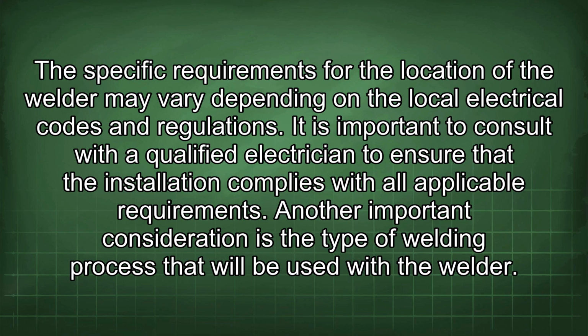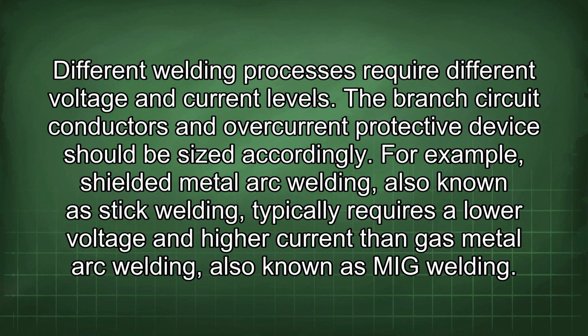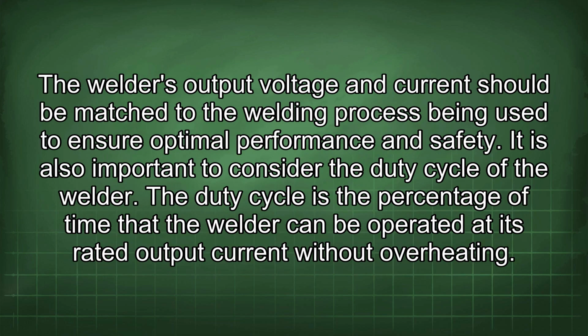Another important consideration is the type of welding process that will be used with the welder. Different welding processes require different voltage and current levels. The branch circuit conductors and overcurrent protective device should be sized accordingly. For example, shielded metal arc welding, also known as stick welding, typically requires a lower voltage and higher current than gas metal arc welding, also known as MIG welding. The welder's output voltage and current should be matched to the welding process being used to ensure optimal performance and safety.